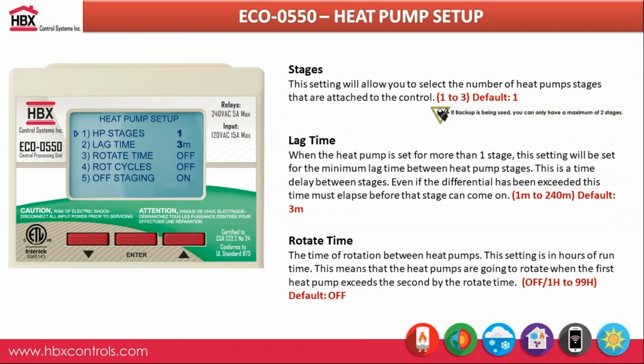So if you were to get into your heat pump stage setup, this really is just asking you how many heat pumps are we utilizing. Again, we can do a maximum of 3. We can adjust the lag time based off minutes, from 1 minute to 240 minutes. And you can also rotate your heat pumps based off time. Again, you would set a certain amount of hours, and then it will rotate, so always firing up that second heat pump or your third heat pump based off that time.